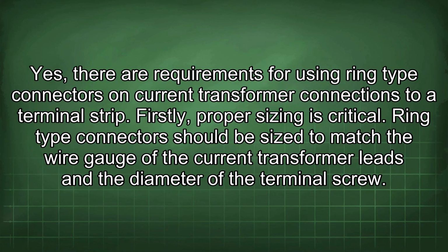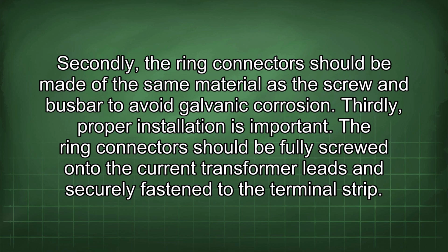Yes, there are requirements for using ring-type connectors on current transformer connections to a terminal strip. Firstly, proper sizing is critical. Ring-type connectors should be sized to match the wire gauge of the current transformer leads and the diameter of the terminal screw. Secondly, the ring connectors should be made of the same material as the screw and busbar to avoid galvanic corrosion. Thirdly, proper installation is important.